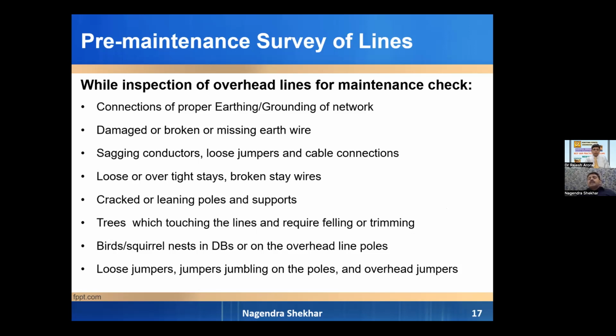What to check while surveying or inspecting overhead lines? Number one, first of all, proper earthing and grounding of the network. It is the most essential thing for any distribution network. Then broken or missing earth wires, sagging of conductors, loose jumpers, cable connections, loose or overtight stay wires, broken stay wires, cracked or leaning poles, pole supports, and trees which are touching our lines or about to fall on our lines, because a lot of poles are broken just because trees have fallen on the overhead lines.